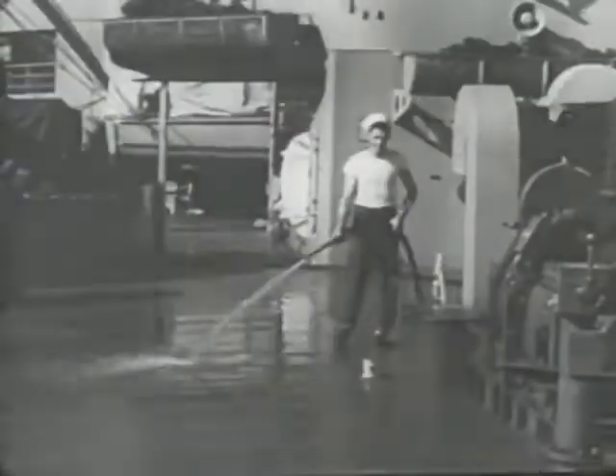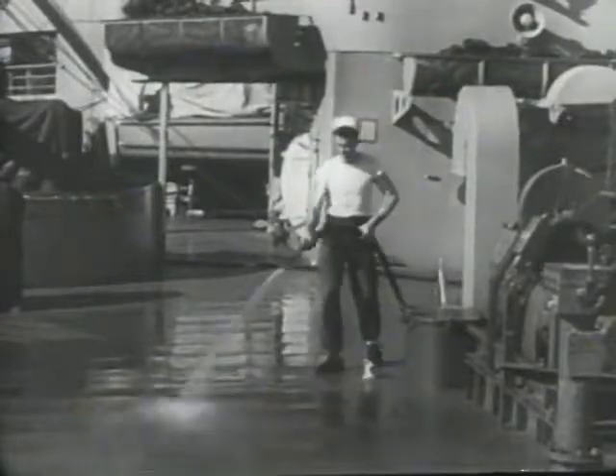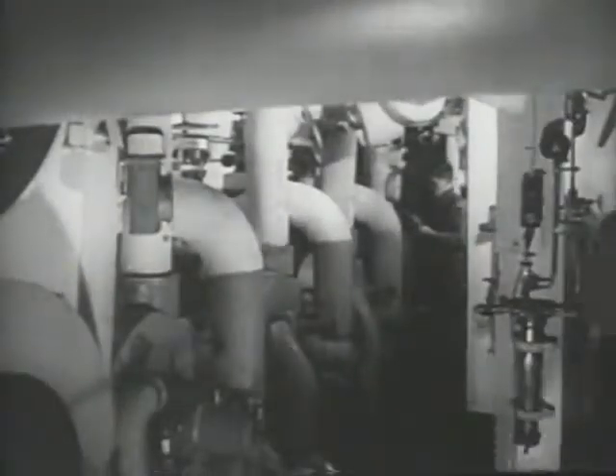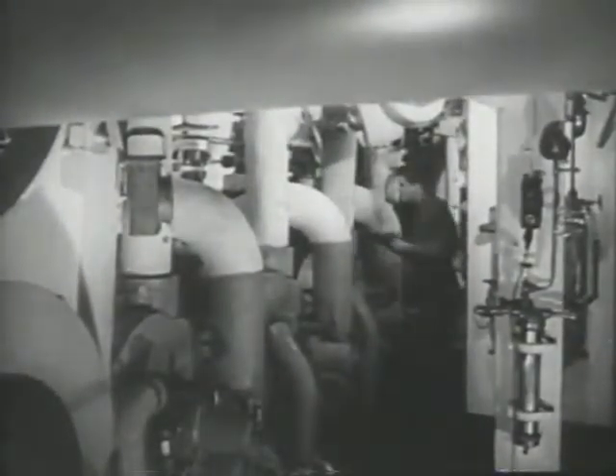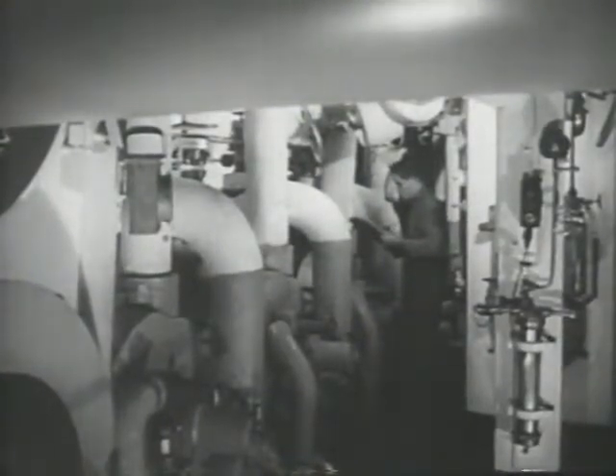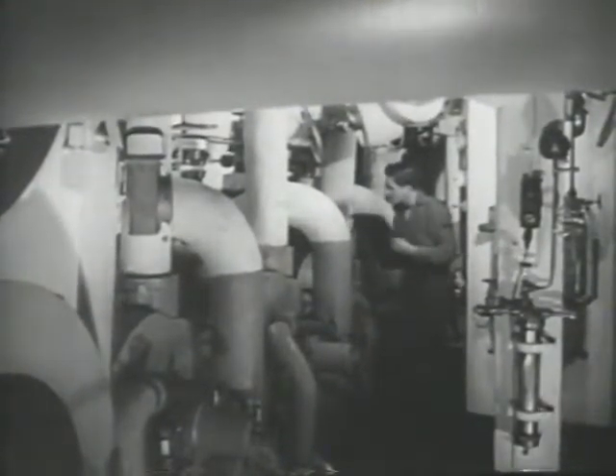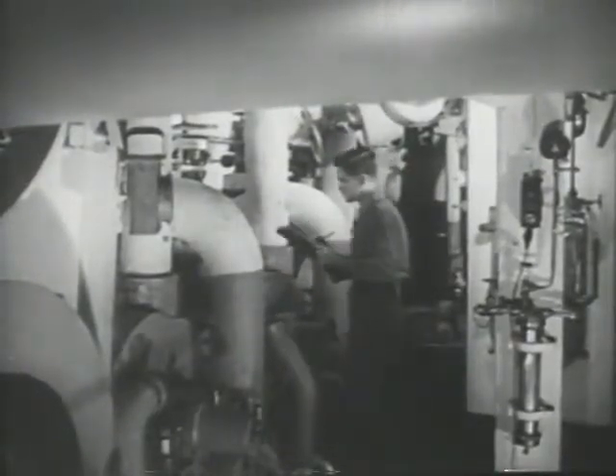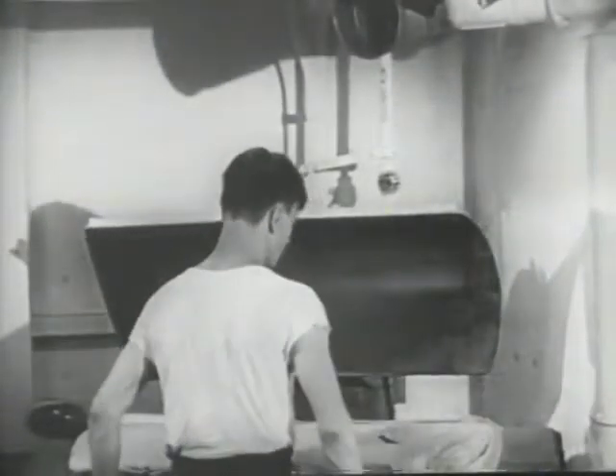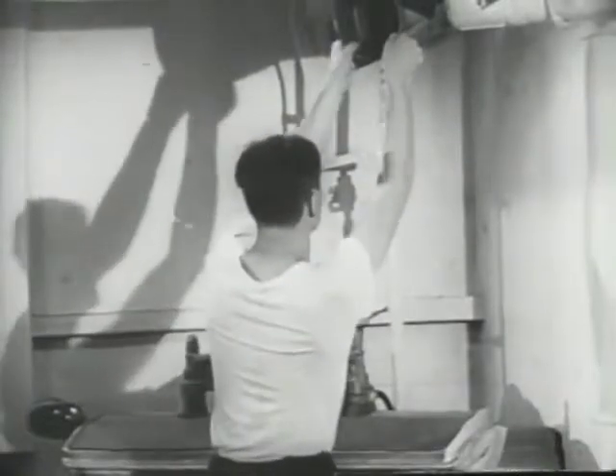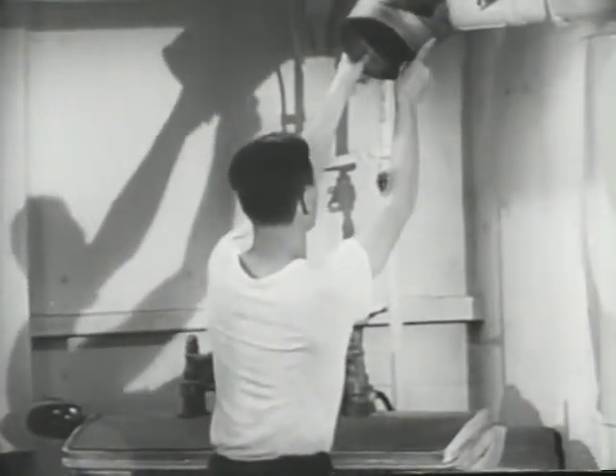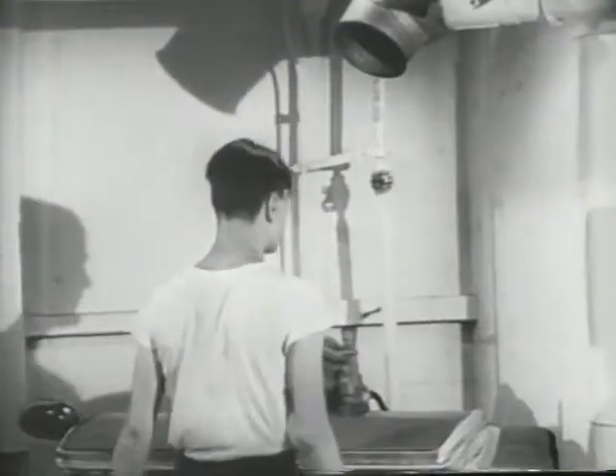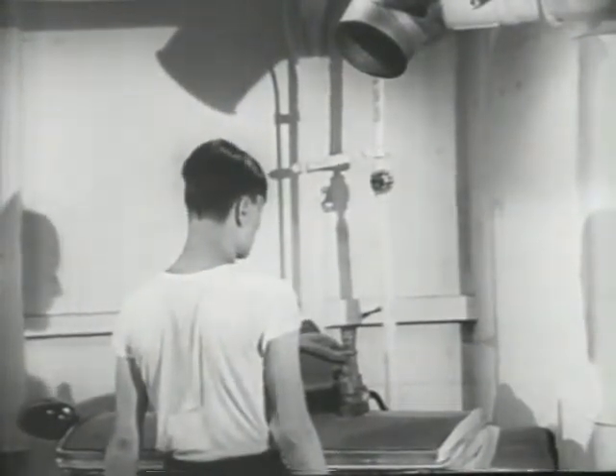Obviously, in extremely hot areas, ventilation air alone is inadequate. The installation of additional bracket fans will help, as well as frequent wetting of decks exposed to the sun. In very hot spaces such as engine rooms, laundries, galleys, and pantries, it is not practical to maintain satisfactory temperatures throughout. So a high-velocity blast of outside air is directed toward operating stations, creating an area of cooler, turbulent air into which personnel can step for relief.